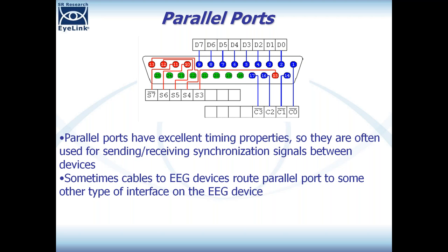In an EEG setup, cables from the parallel port on the display PC sometimes route to a parallel port on the EEG device — on the EEG amp or some kind of EEG communication interface box. Sometimes EEG devices require special cable with a parallel port on the display PC end and some other connector on the EEG device end, like a 9-pin connector. Of all the EEGs I've seen, they can receive synchronization pulses that originate from a parallel port.